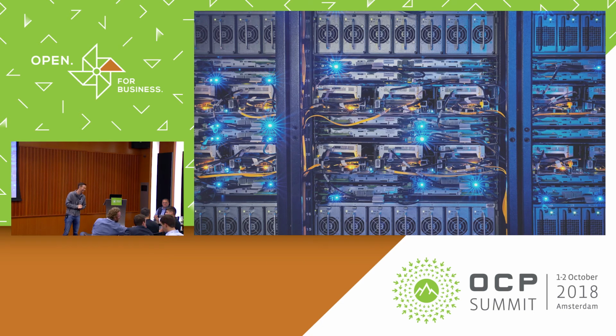I can try. I used to work for a big colocation company, and we also have customers that run APC systems, and they run 50 kilowatt steady load per 19-inch air-cooled rack. Works fine. So the need for it will be there, but it's not here today. We can run 50 kilowatts in an air-cooled rack without any problems. So are there any other arguments against adopting liquid in that sense?